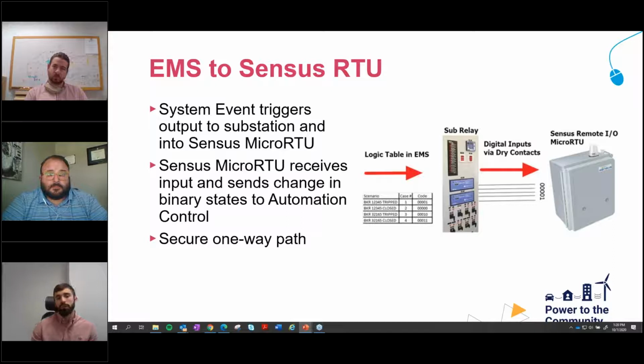This is where I mentioned the one-way flow. This was super important to us, just in case there's any issue with cellular. You always hear it's a little less secure, so we wanted to make sure that if there are any issues on cellular networks, it couldn't get back to our EMS system. Because the micro RTU offers dry contacts to connect into, there's no way to get from the micro RTU back up into your EMS system, and that's really giving us a lot more security. This RTU is installed in one of our substations, but really you could put it anywhere you have service. So, next slide.